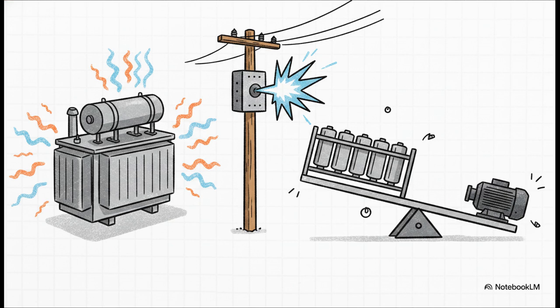Utilities usually target correcting to a power factor of 0.95 to 0.98. You don't want to overcorrect to 1.0 because that can cause severe voltage rise issues. In fact, quick scenario for you. Say a plant's power factor drops from 0.95 down to 0.70 overnight, but the total load hasn't changed. What happened? Most likely, a capacitor bank tripped offline, like a blown fuse, and the plant lost its reactive power support. That is a real-world troubleshooting pattern that happens all the time.